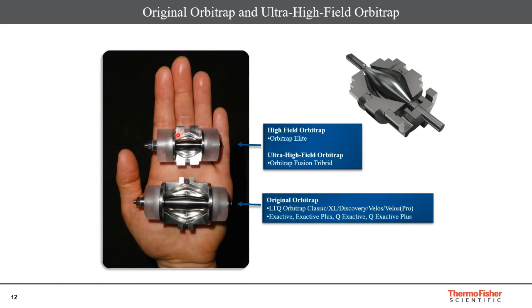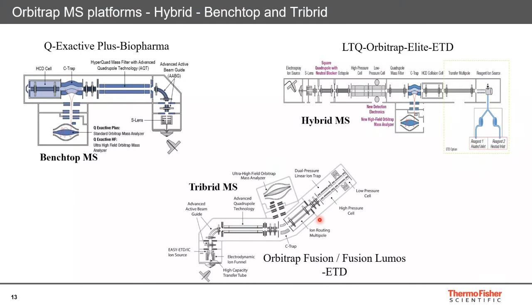The difference is that in this instrument, you have quadrupole and the Orbitrap, right? Whereas in this instrument, the one in the right-hand side top panel, you have the ion trap and the Orbitrap. In the bottom one, we have quadrupole, ion trap and the Orbitrap. That's the difference, the number of functional analyzers within a given instrument. If it has two functional analyzers, we call it a hybrid instrument, top panel. And if it has three functional analyzers, quadrupole, ion trap and Orbitrap, we call it a tribrid instrument, as simple as that. So what does it mean? It means this particular instrument has much more analytical capability. It could be multiple fragmentations, or sequential fragmentations, MSn. All these add-on analytical features are available in tribrid. So that is the difference, fine.